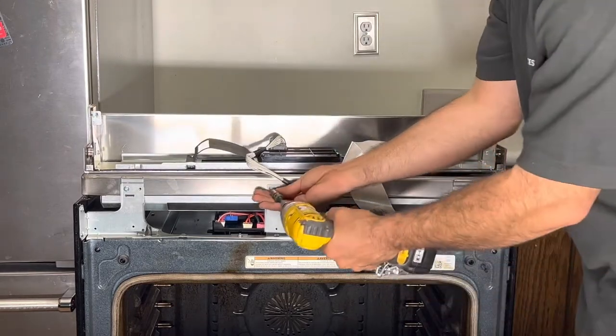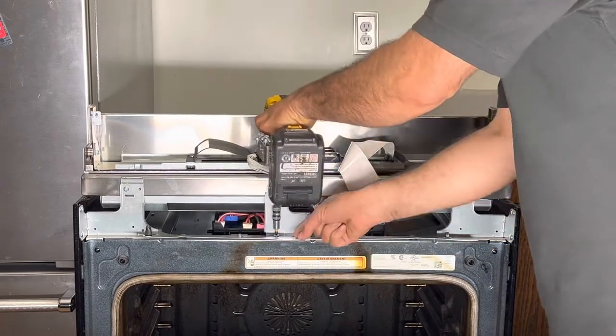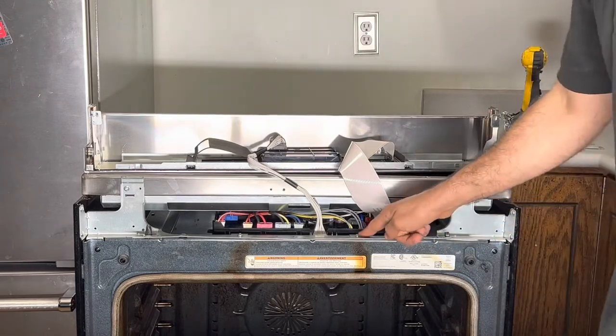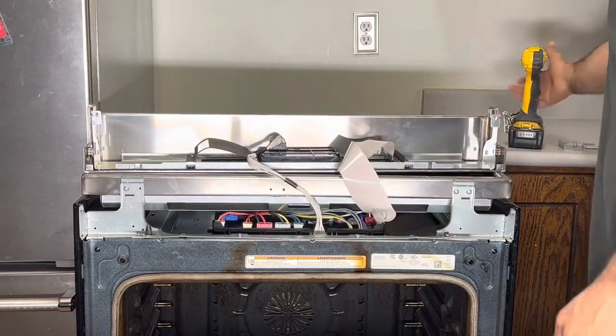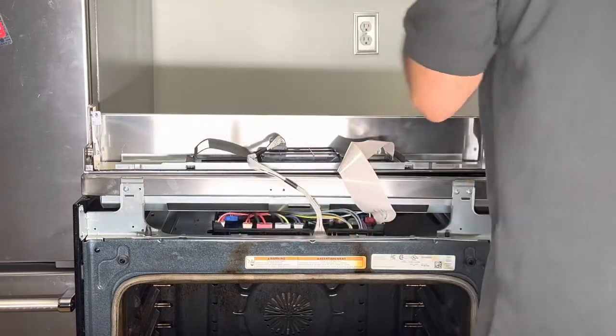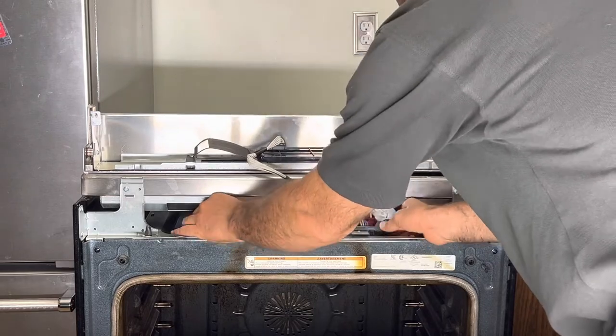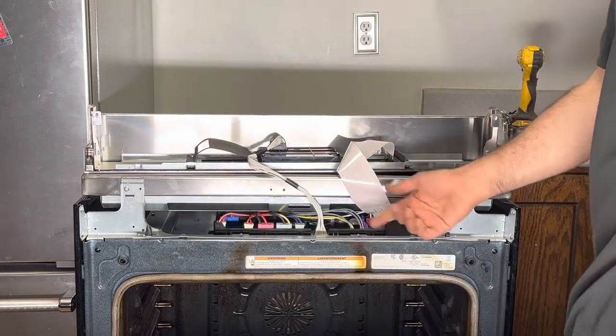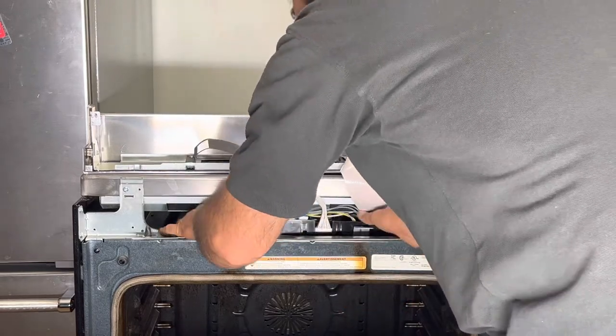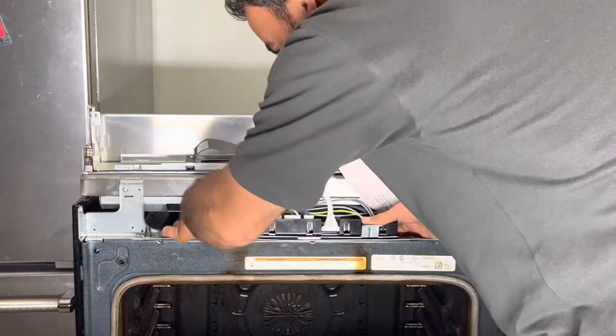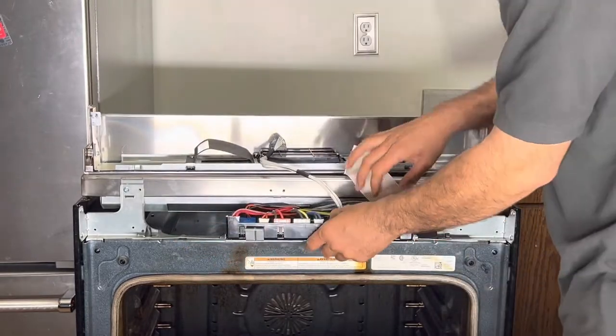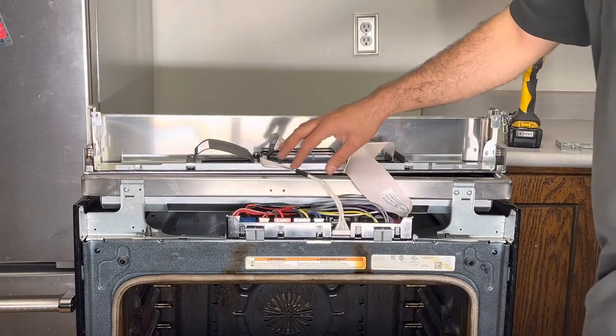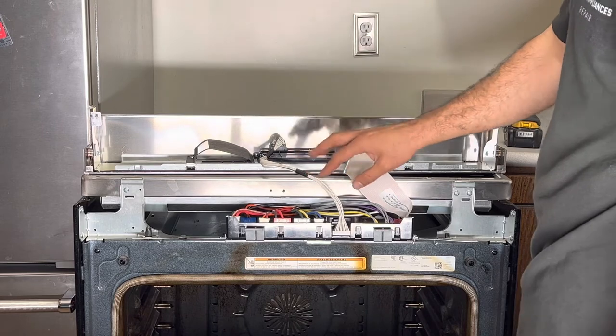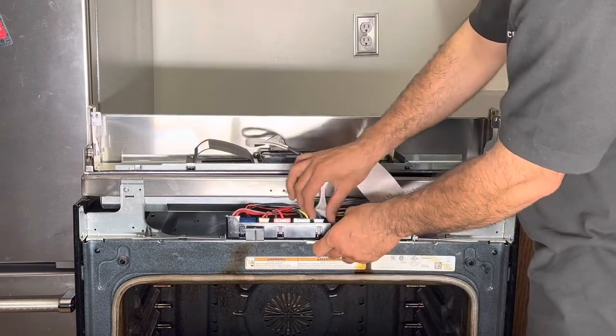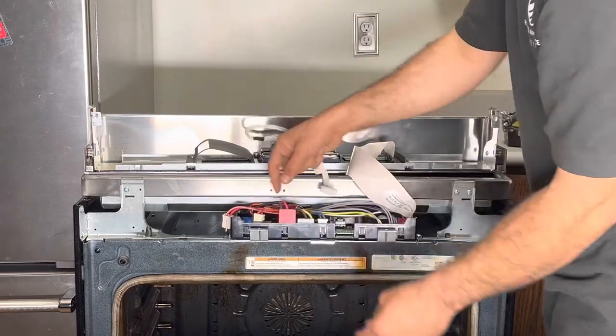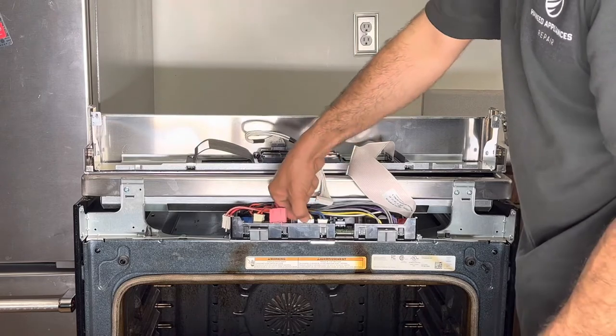Okay, so this piece comes off, it's in front of the control board. And then there are 2 other screws that hold the control board in place. You will take those off. And then the control board comes out, the main control board. All the wires are color-coded, but you can still take pictures if you're not feeling comfortable doing this. Disconnect. Do not pull on the wires, only pull on the connector.